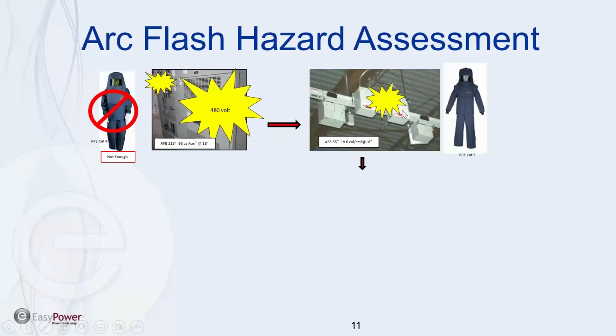And people think, well, I'm only changing out a 15 amp fuse. Well, your bus plug is on the bus duct side, and that's going to be this 18.6 calories. So that means every one of these cabinets has that calorie rating inside. So even though it's a 15 amp fuse, it's not a small-time arc flash hazard on the line side, or the bus side, of that fuse. It's still going to be high.